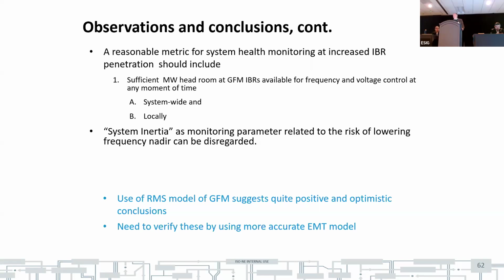And currently, a lot of research and publication treats system inertia as the monitoring parameter for system health. At least that type of study showed that that parameter is really irrelevant, because what is really important is how much headroom for control you have in the system. So again, results are very optimistic, and they are valid as long as the RMS model for the inverter is correct.